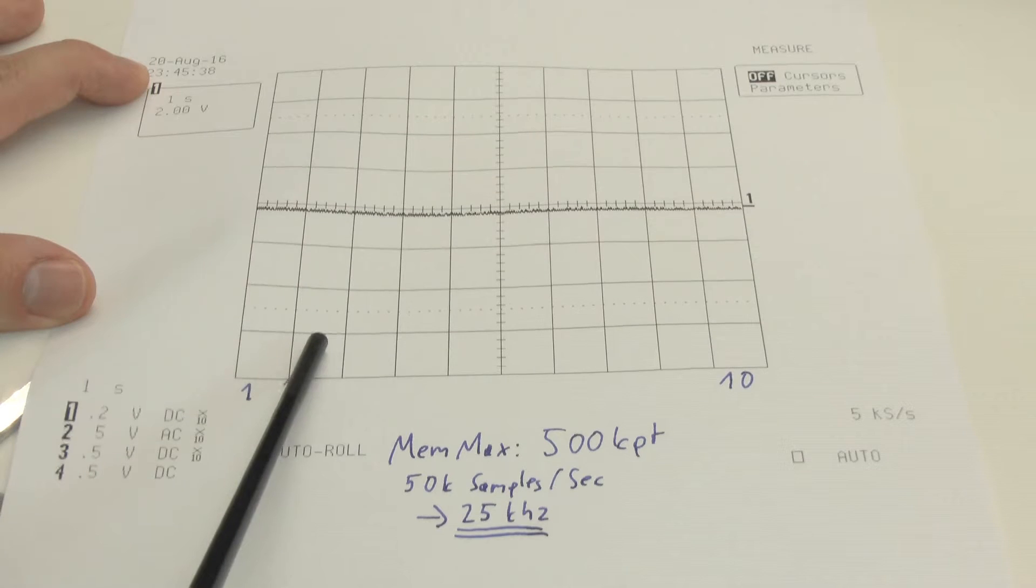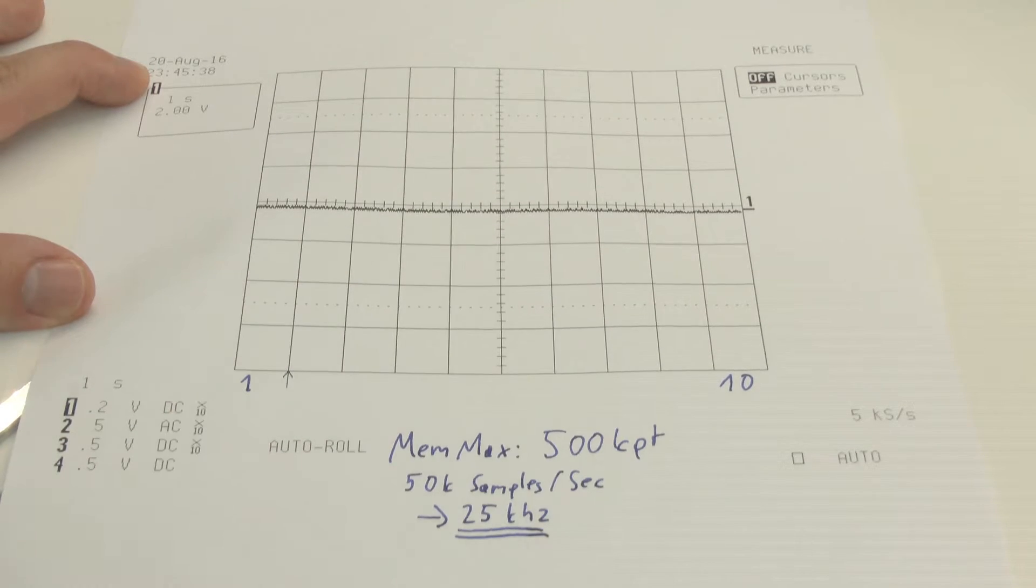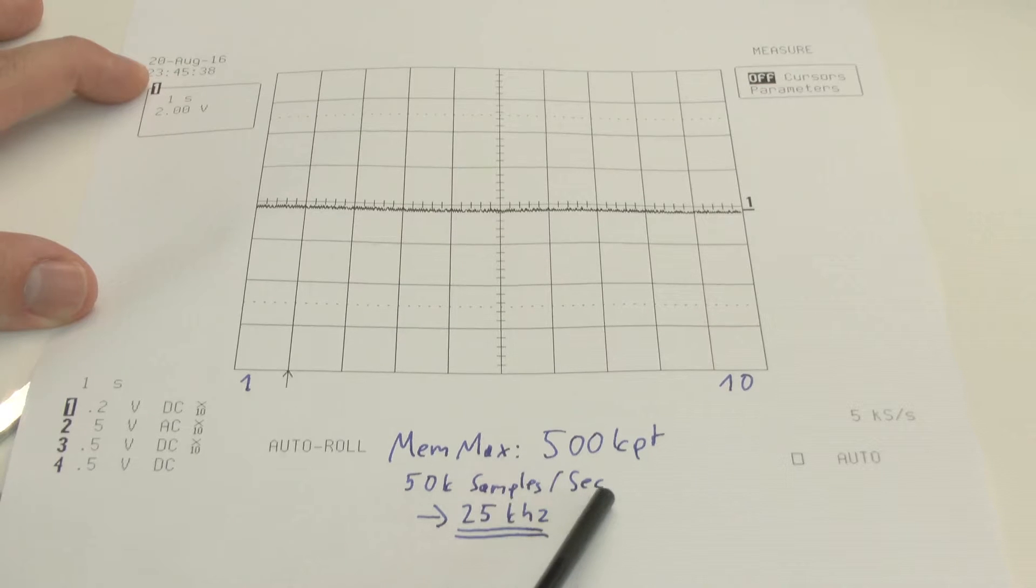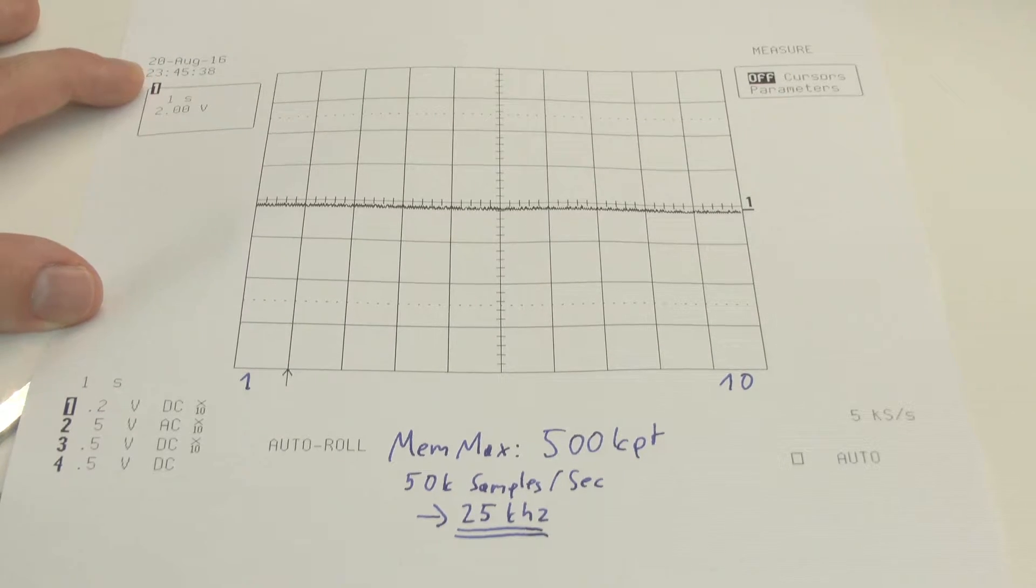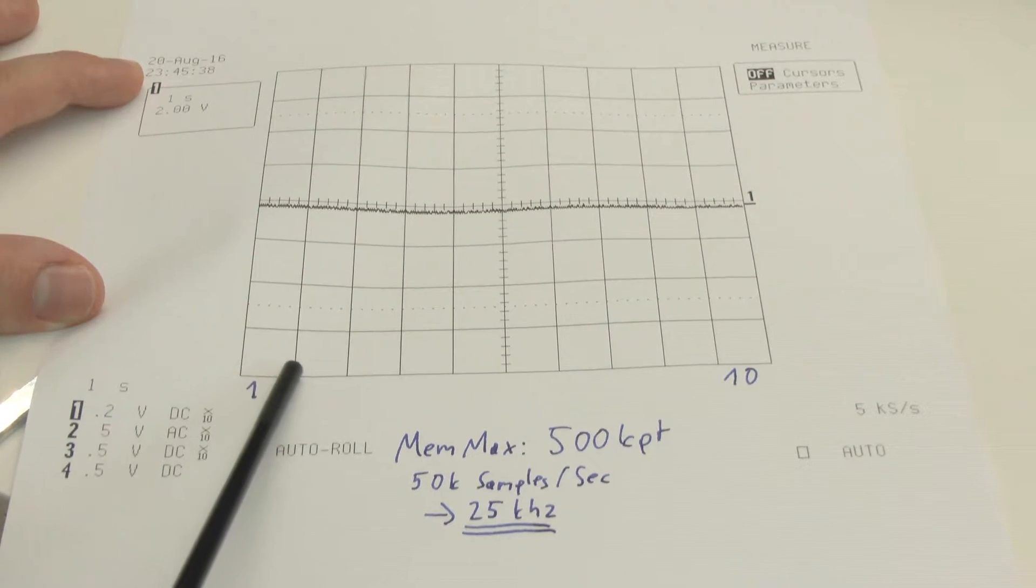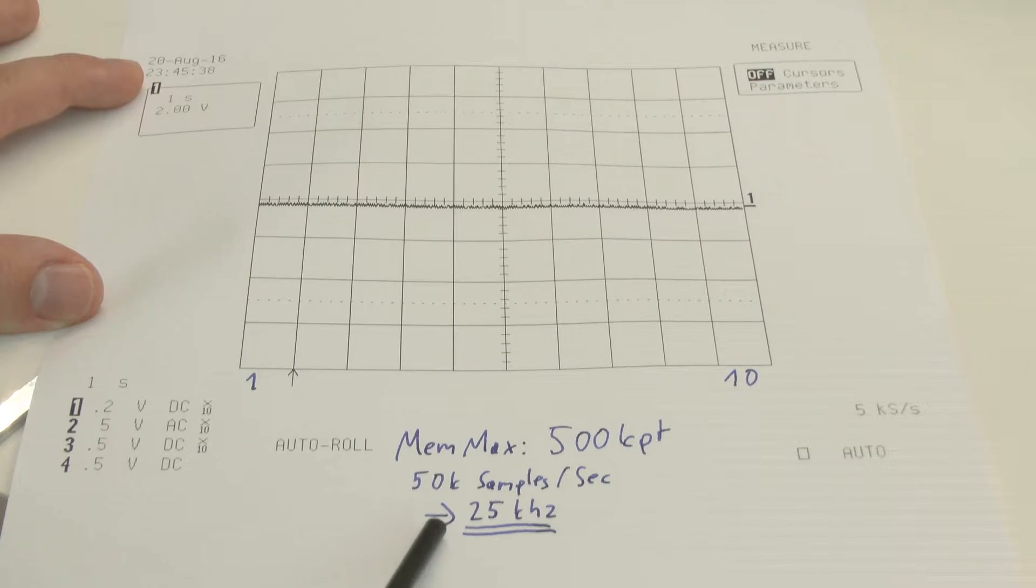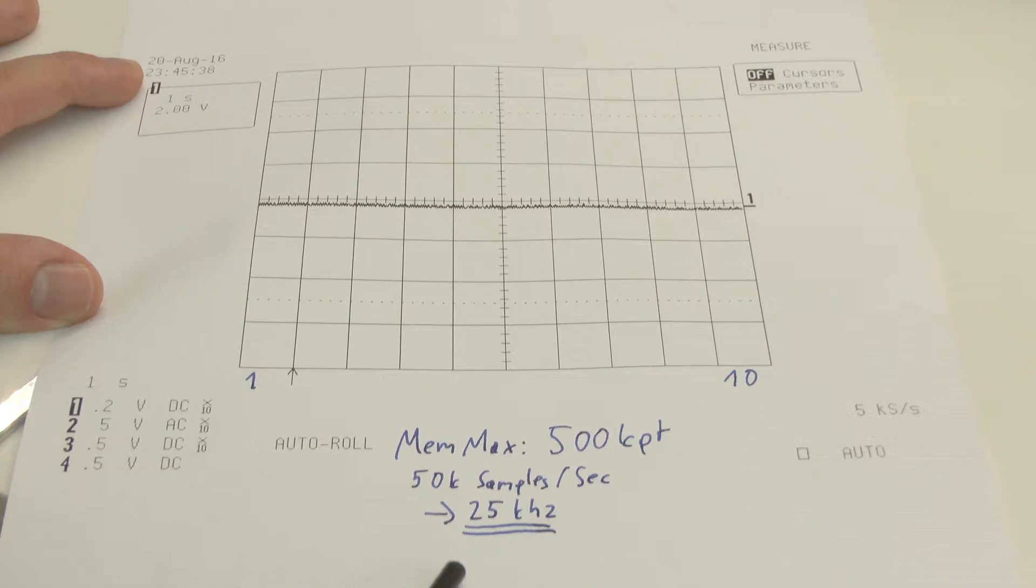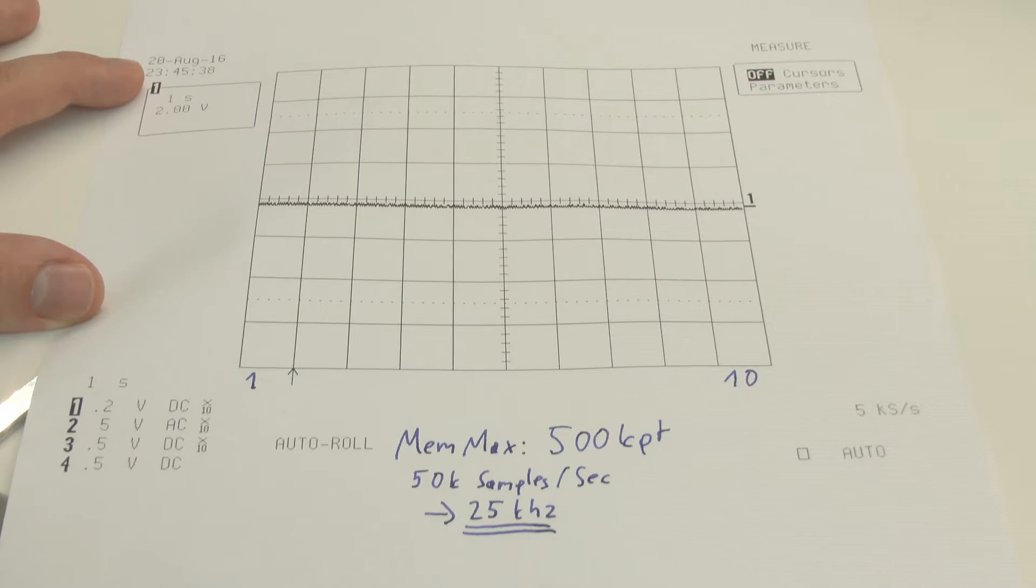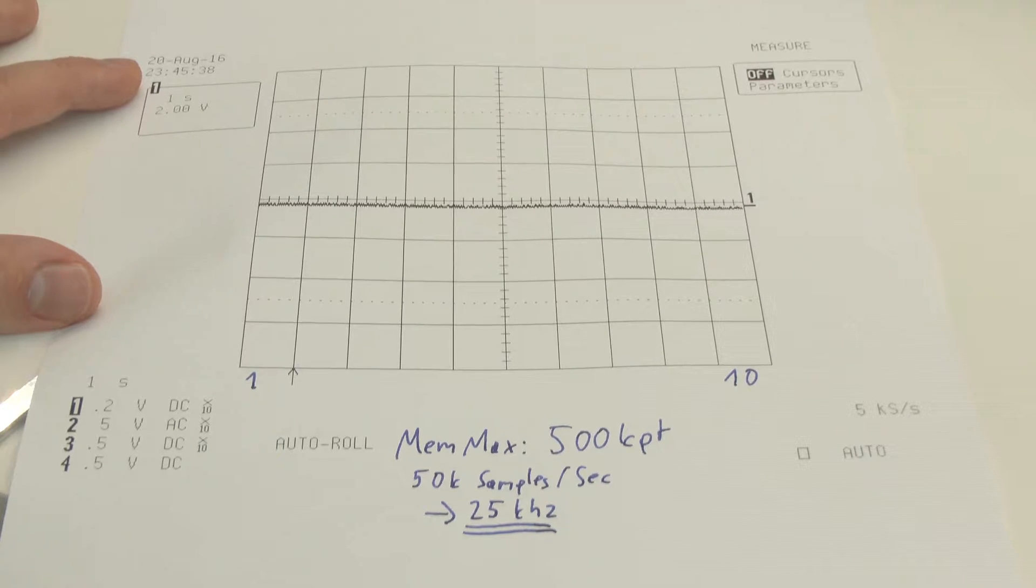You see here, we've got a total of 10 boxes, and we've got a theoretical maximum memory of 500 kilopoints in dual channel mode. So this tells us that for each one of these boxes, we've got but 50k points, which according to Nyquist's theorem, limits us to just 25 kilohertz sampling rate.